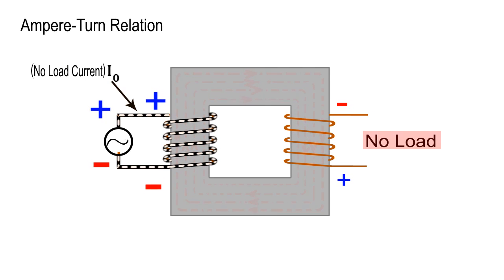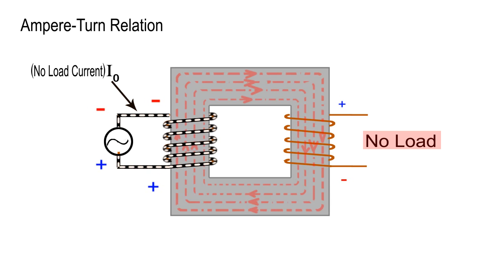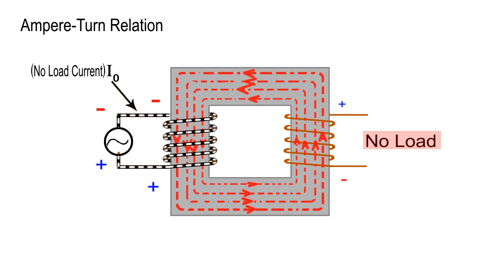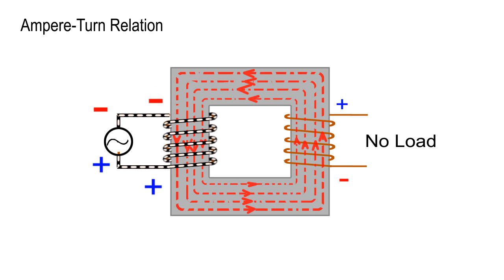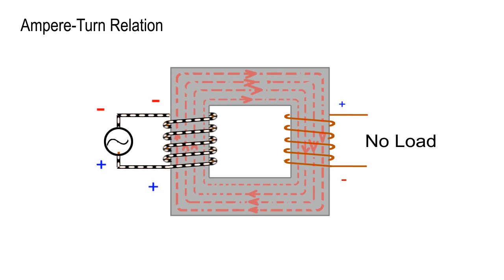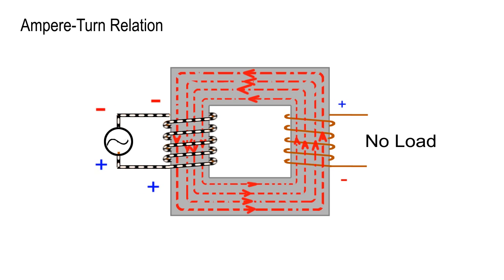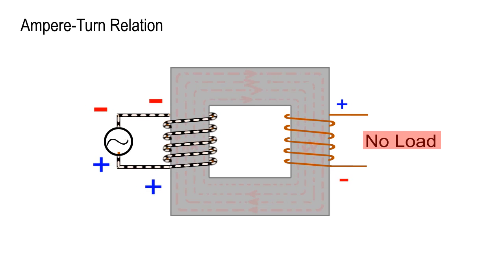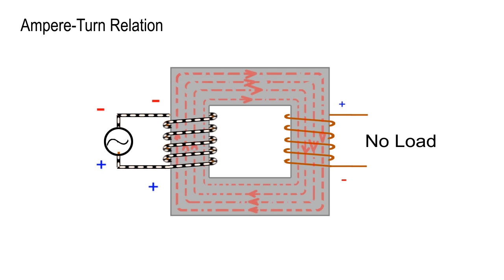Thus, the exciting current or no-load current I0 is small in magnitude, ordinarily being 3% of the rated current. The exciting current I0 is of small magnitude and generally differs considerably in phase from the total primary current. Therefore, it is normally neglected in comparison with the total primary current.